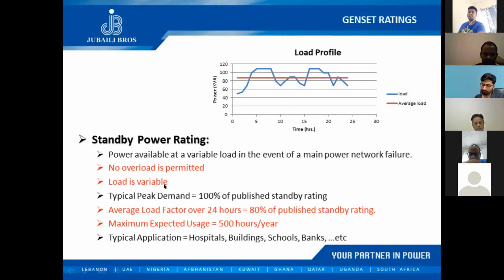My load is also variable. If you look at this load profile, it's varying with time. It's not constant, so it's similar to our prime application. It is a variable load. The typical peak demand is 100% of the published standby rating, which is 110 kVAs, not 100 kVAs.